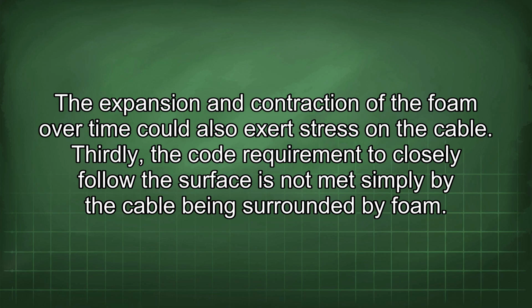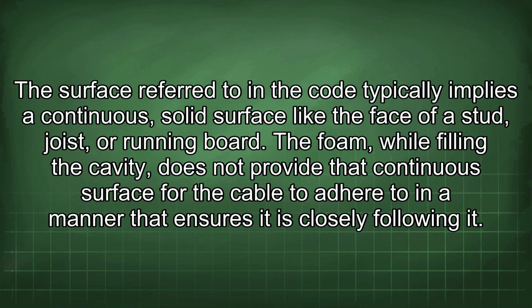Thirdly, the code requirement to closely follow the surface is not met simply by the cable being surrounded by foam. The surface referred to in the code typically implies a continuous, solid surface like the face of a stud, joist, or a running board. The foam, while filling the cavity, does not provide that continuous surface for the cable to adhere to in a manner that ensures it is closely following it.